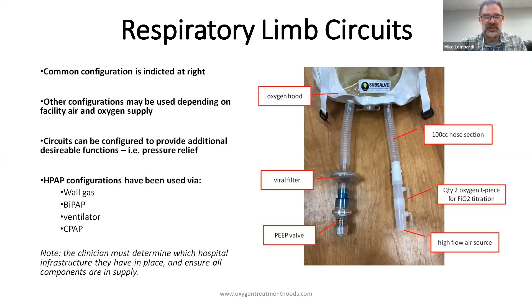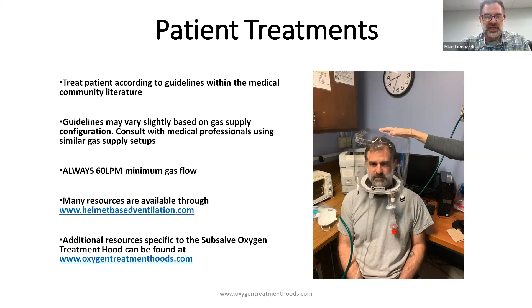Okay, so I'll leave patient-specific questions and protocols to the physicians on board, but I'll mention that the guidelines can vary slightly based on the gas supply configuration. One key thing to point out is that we always want a minimum 60 liters per minute of flow through the hood, and that's to minimize the risk of carbon dioxide rebreathing. There have been publications that have proven this out, and as such, that's a really excellent benchmark for a minimum gas flow through the hood. And there are also great treatment protocol resources available at ARCA's site, helmetbasedventilation.com, and then I am collating additional resources related to the subsalve hood at oxygentreatmenthoods.com.